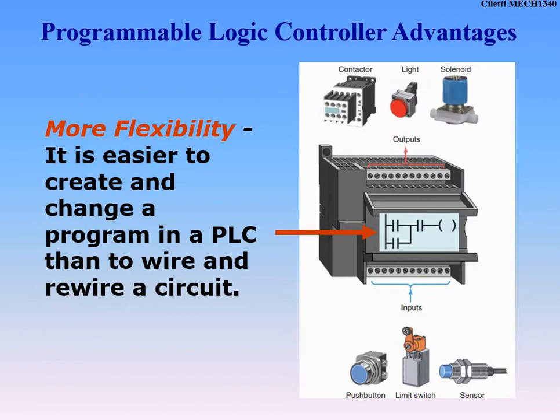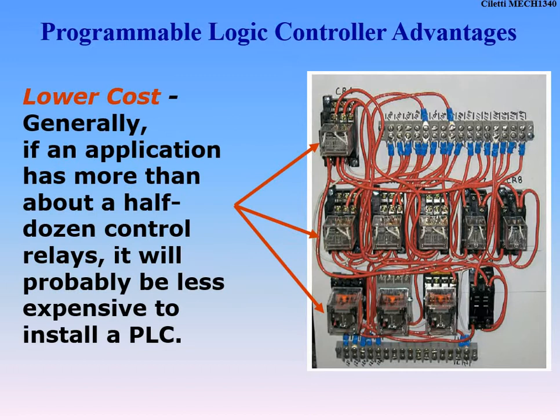PLCs are much more flexible. It's easier to change a program in 30 seconds and re-upload it than to go out and rewire an entire relay panel. With PLCs, I can work remotely from home, tie into the PLC, change a code, and everything will work. We don't have to physically rewire anything because everything is addressed to the inputs and outputs on the PLC. We just change how the control works — everything's wired once. Much more flexible, easier to work with, and much easier for troubleshooting.